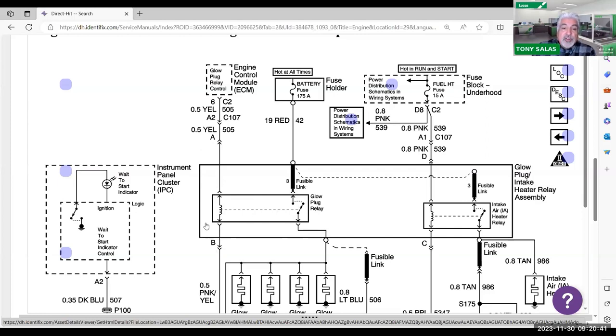Not only across the coil side, but also the switch side, to see if you got high resistance there on those contacts. Now a lot of us cheat, I know, I get it. I do it sometimes myself, if I got another relay I'm diagnosing, I'll just swap it with another relay. But this is a big relay, a different kind of relay. No matter what, you're supposed to do a voltage drop across these.